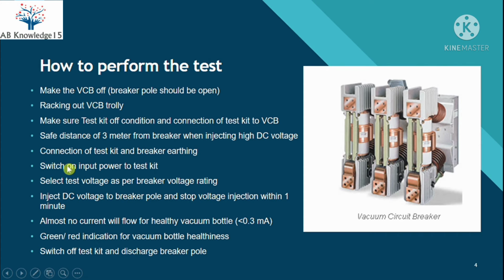Switch on the input power to the test kit and select the desired voltage as per the breaker voltage rating. For selection of the test voltage, you may refer to the breaker rating. Suppose this breaker rating is 11 kV. There is an equation: 2 times kV plus 1. So if the breaker voltage rating is 11 kV, multiplied by 2 it will be 22 kV, plus 1 will be 23 kV. So for an 11 kV breaker the test voltage will be at least 23 kV for carrying out this vacuum interrupter test.